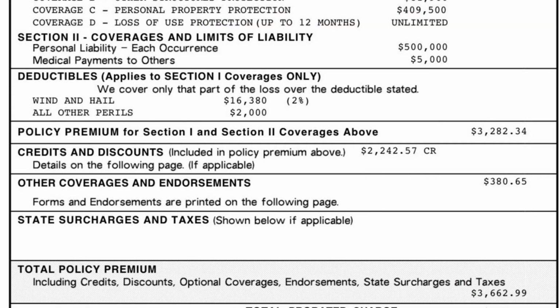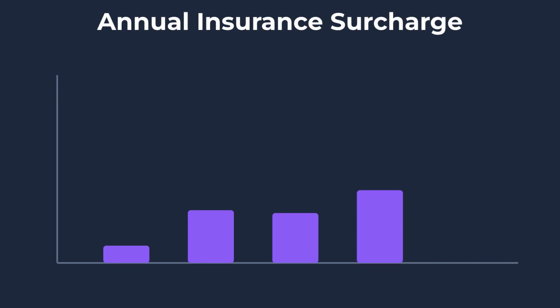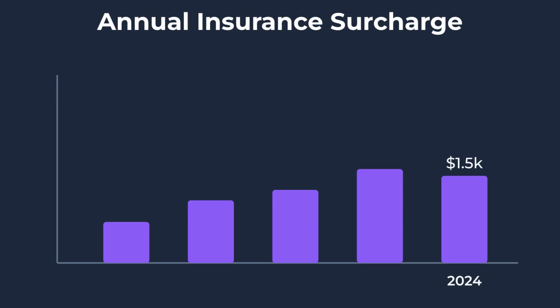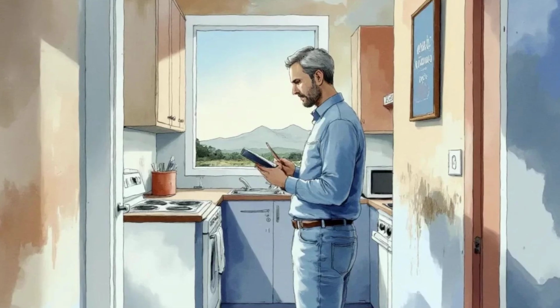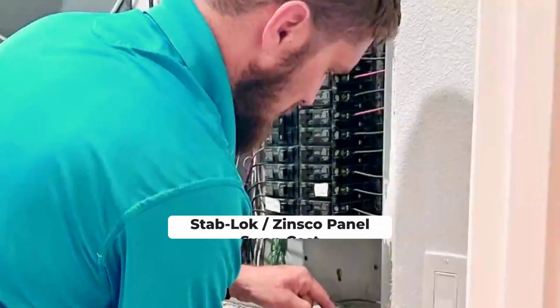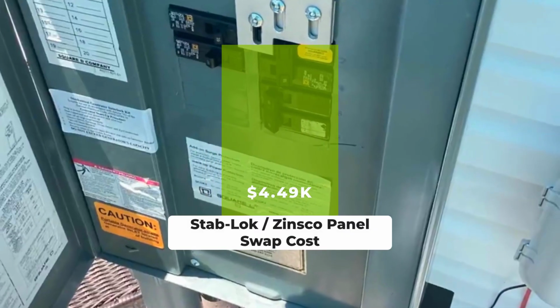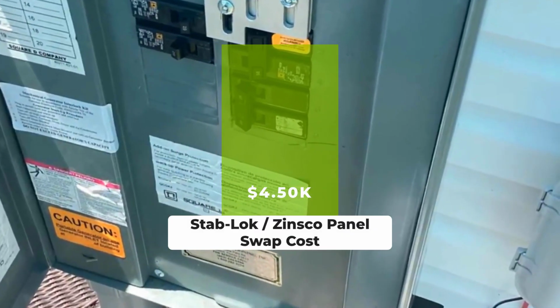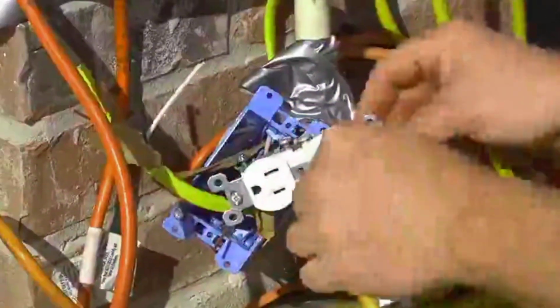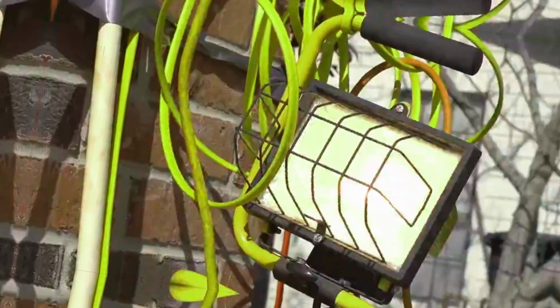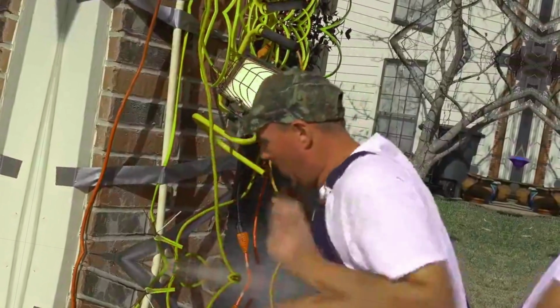Insurance companies have taken notice. Many will refuse coverage outright or add an annual surcharge of $500 to $1,500 until the panel is replaced. Inspectors often note the brand in their report, but rarely spell out the financial or legal consequences. Replacement costs for a modern, code-compliant panel run between $2,500 and $4,500, and the work must be performed by a licensed electrician to satisfy most insurers.